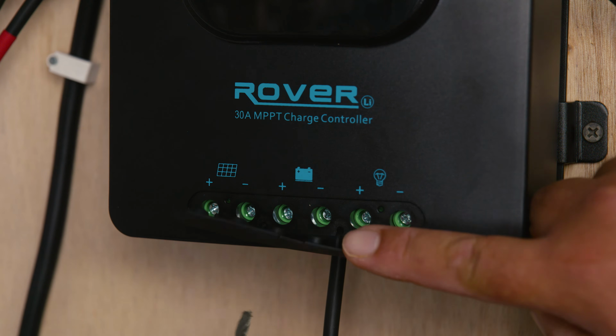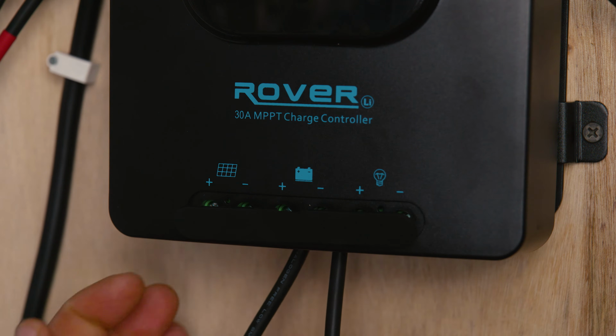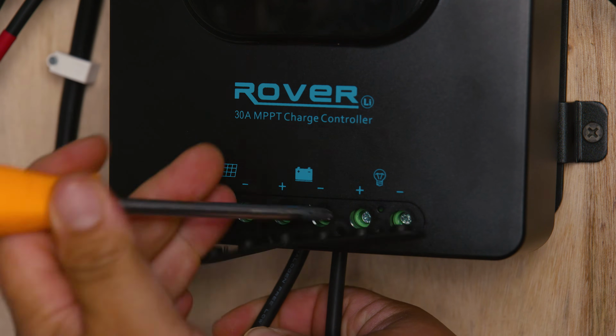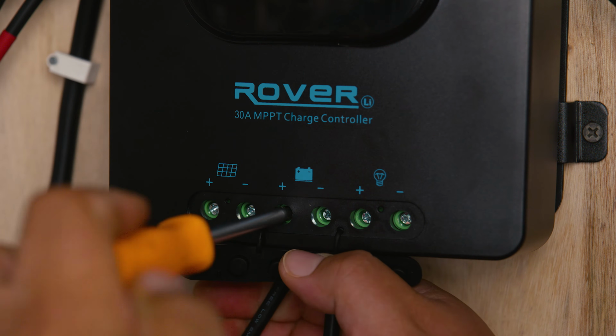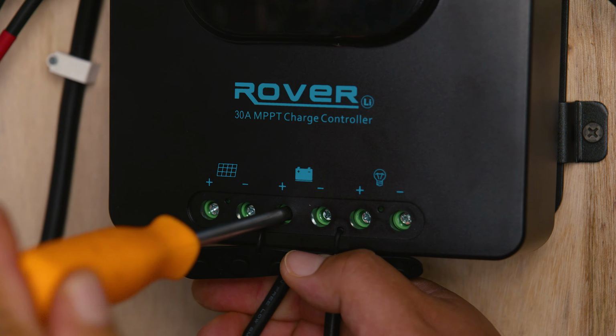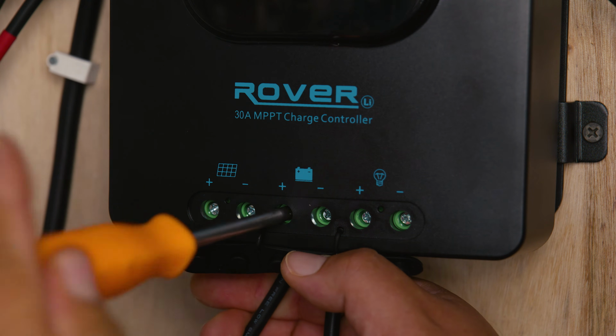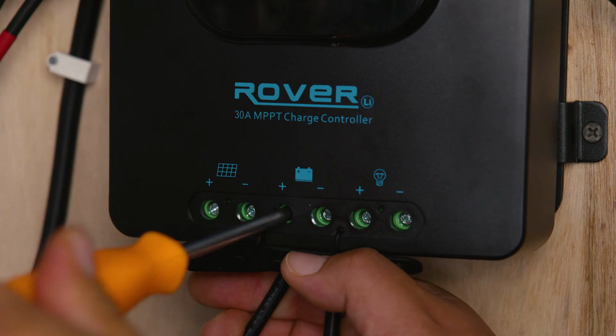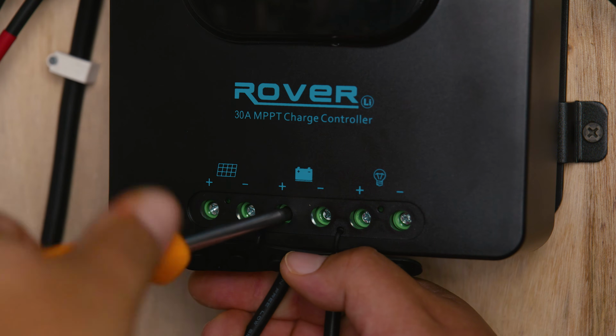Once we feel it tight, that should be good enough. We always want to do the pull test after tightening the screw terminal to make sure the wire is not coming out. Pro tip: after the first use, a day after, you always want to check the wires to see if they need retightening.